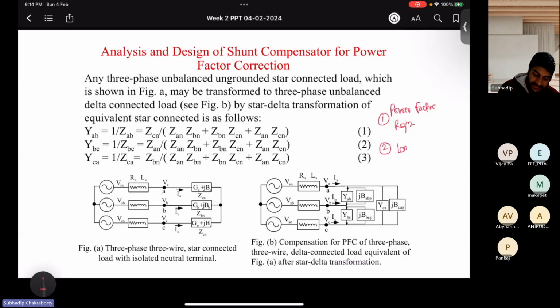And another thing is load balancing. You want to balance the connected loads such that the effective loading on all three phases is the same. Why is this important? Load balancing. Anyone? To avoid stress on any particular phase of the equipment.